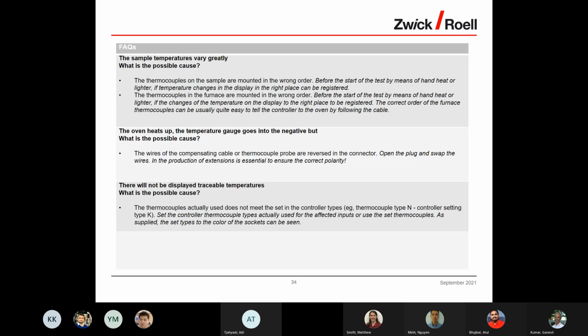There are no traceable temperatures displayed. What is the possible cause? The thermocouples actually used do not match the types set in the controller. Set the controller to the thermocouple types actually used for the affected inputs, or use the set thermocouples as supplied. The set types can be seen from the color of the socket.